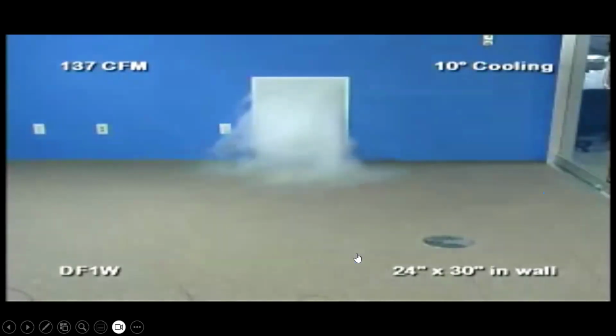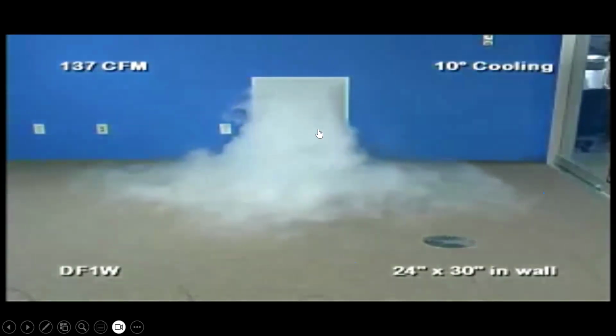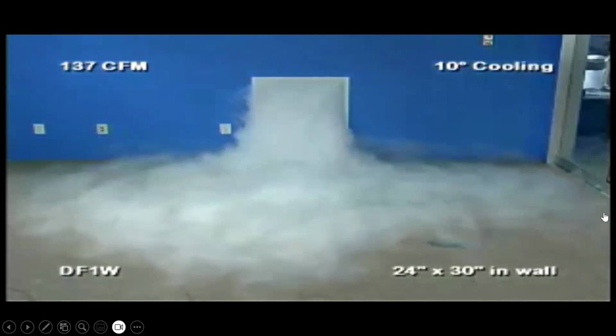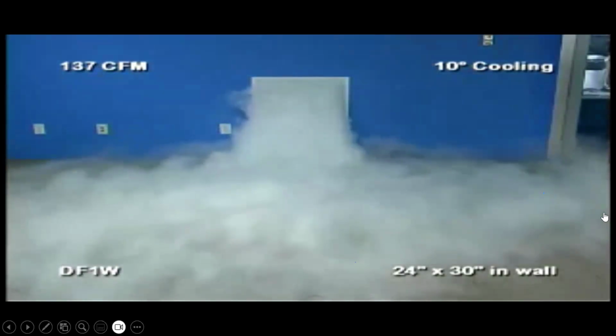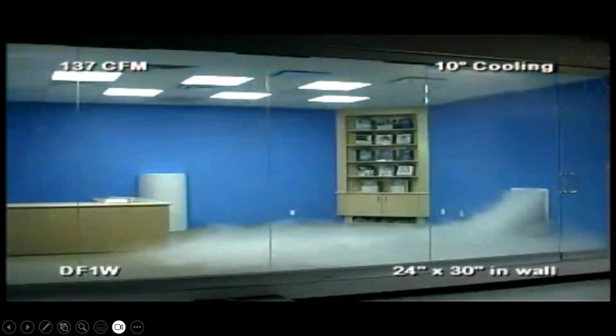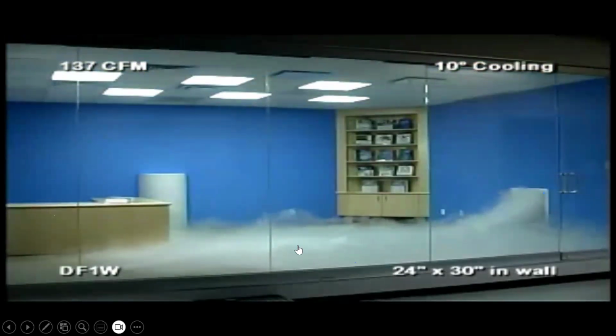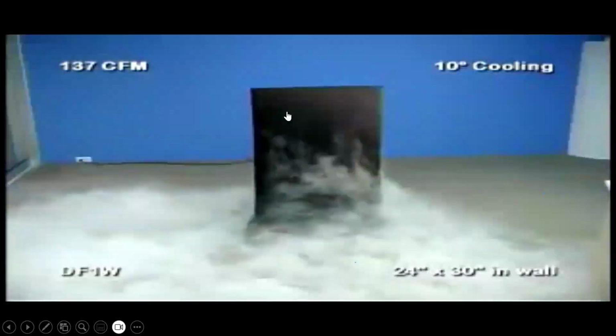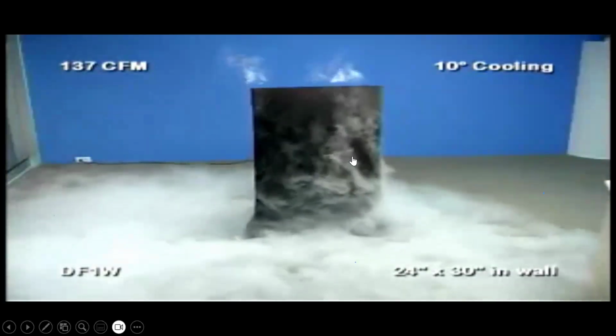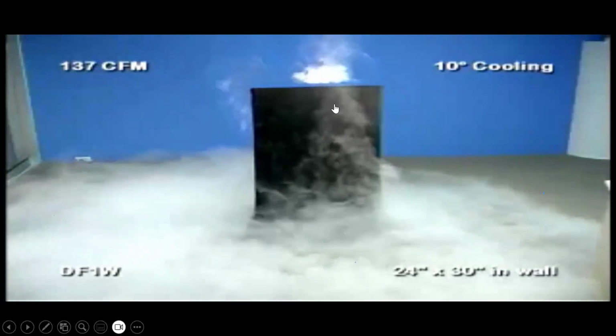So let's take a look at what it looks like. Here you see the cool air enters the space and it spreads along the floor. It is just moving forward at a very low velocity. It spreads evenly across the floor. It can go around obstacles. Nothing comes in the way till it comes in contact with a heat source. Now this is a heat source, and the air gets warmed up, and as it gets warmed, it rises up. And you can see that thermal plume over there.